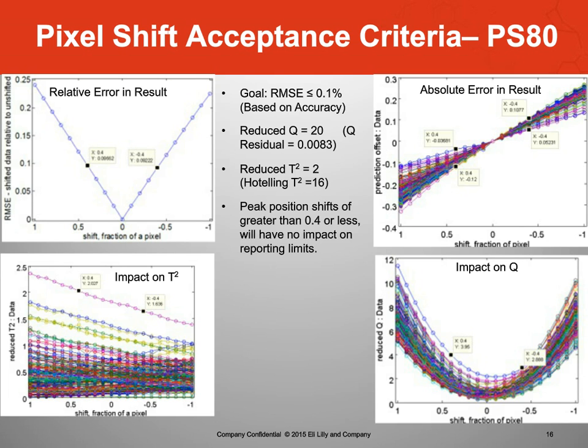Just to remind you, it was on one of the slides that the spec is 9.5 to 10.5 for tween. For Triton, it's 24.5 to 25.5. That's the range we need to be in as far as reporting values. Again, look at the impact on T-square. A 0.4 shift plus or minus is going to be less than the acceptance criteria for T, which is right around 2. And for Q, my acceptance criteria is 20, which is way up in this region, and we're well below that. So again, 0.4 works for both models and for what we'd expect for cyclohexane.